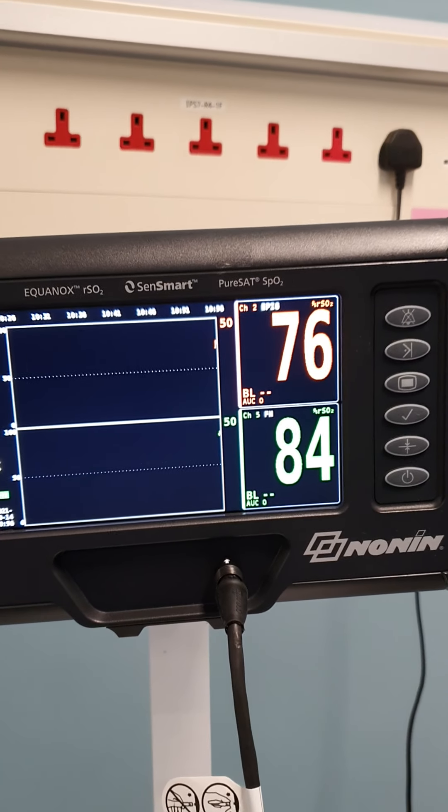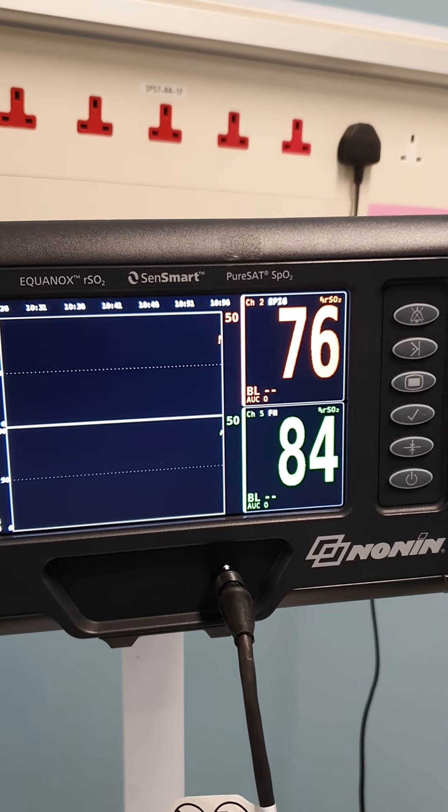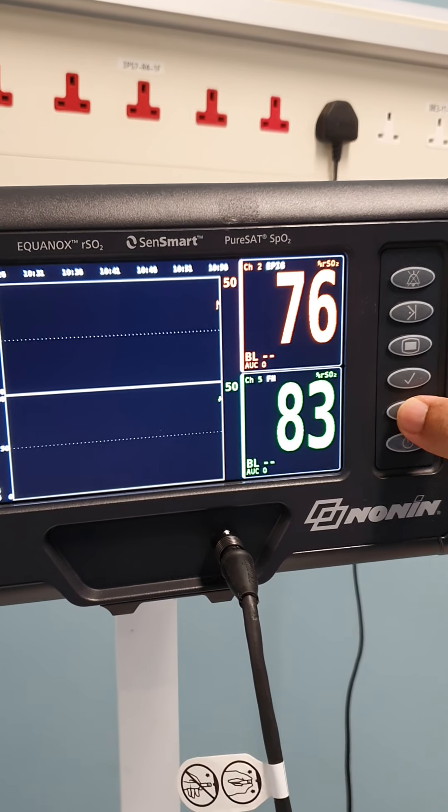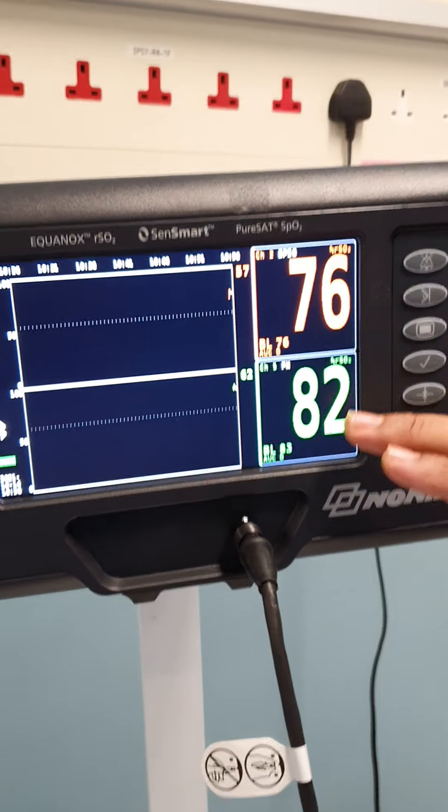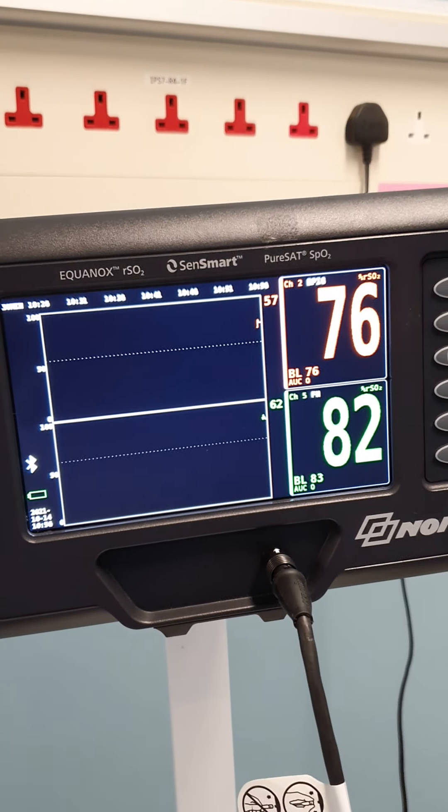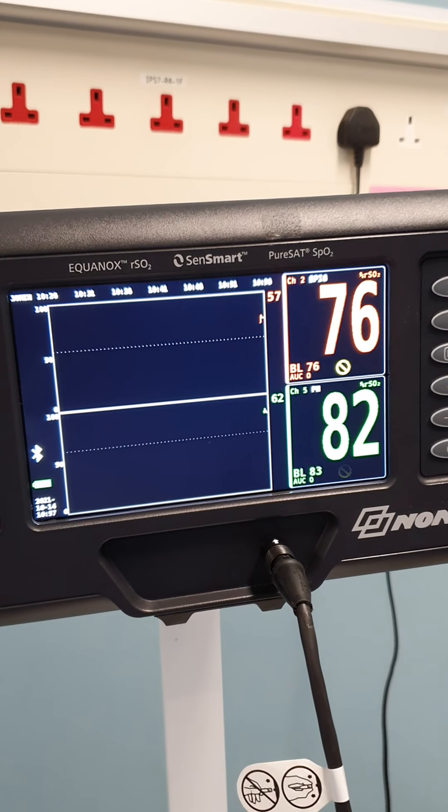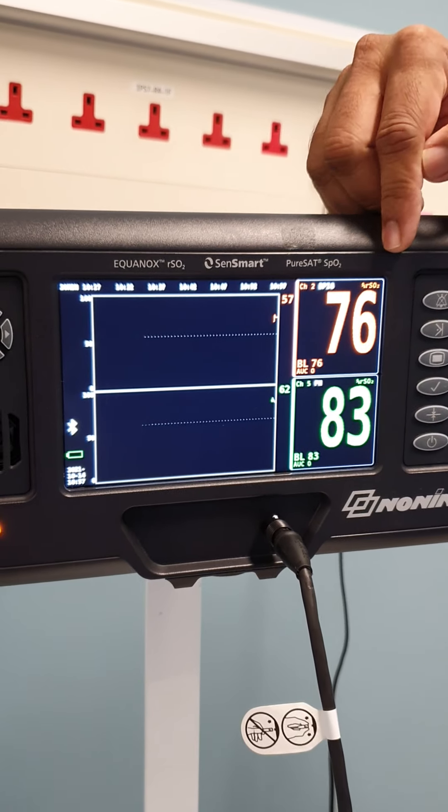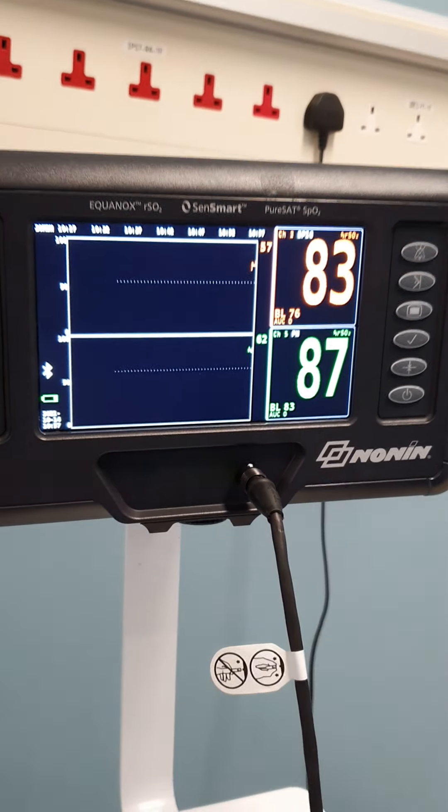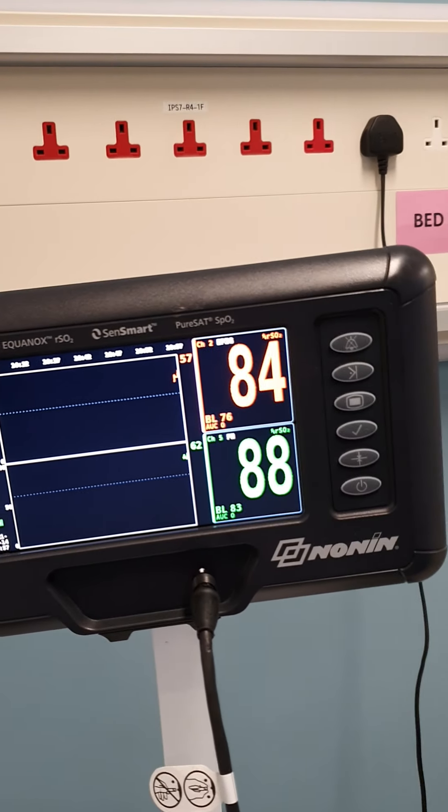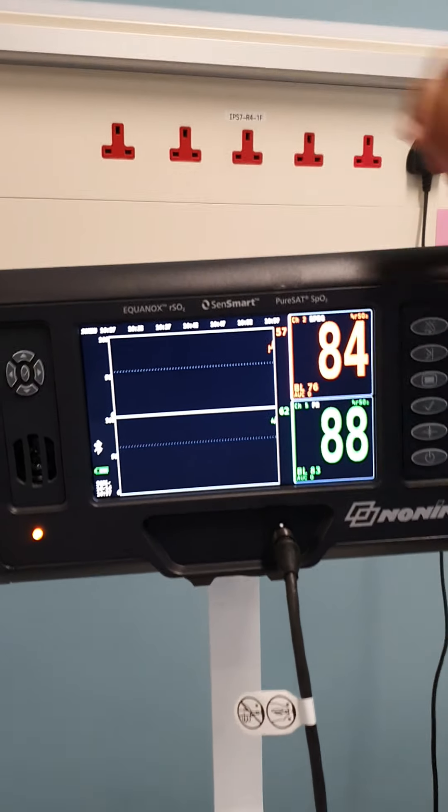So now what I have to do is make a baseline. I'm seeing that my patient is stable. I want to create a baseline. So I'll just click over here. It will ask me whether you are okay with the baseline. I'll say yes. You see my baselines are already selected. And now after the baseline is selected, the machine sets an alarm of 25% for your baseline. You can see in the center now. Depending on whatever the baseline is, it has already by default selected the alarm. But you can change it. That you can change, no issues.